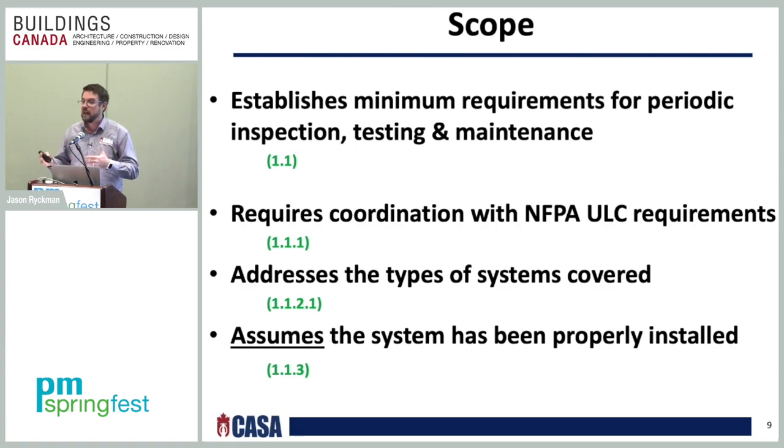Now, that doesn't mean that an inspector who finds any design or installation deficiencies can't record them to the owner, but it would be as a separate document, not on the inspection form. It's basically an informational type of document, just telling the owner or owner's representative that you do have design and installation deficiencies that you need to take care of.